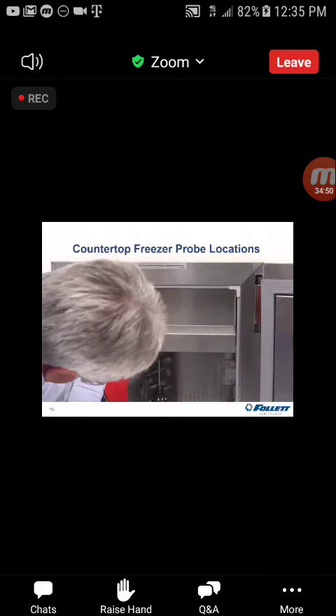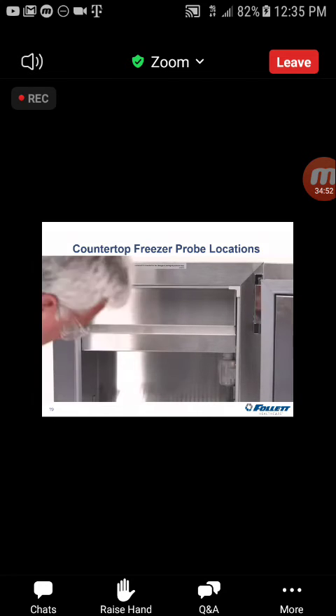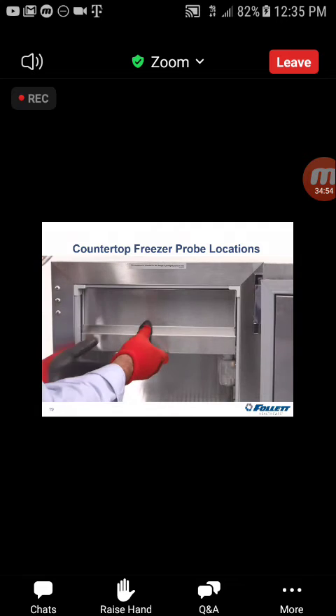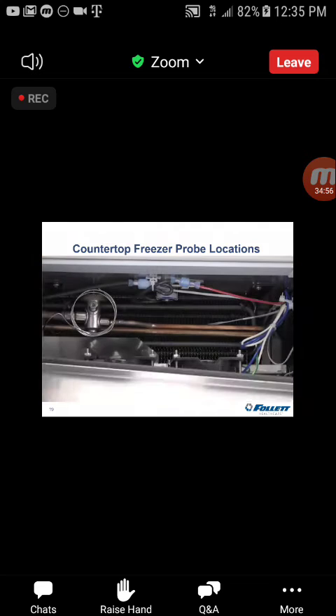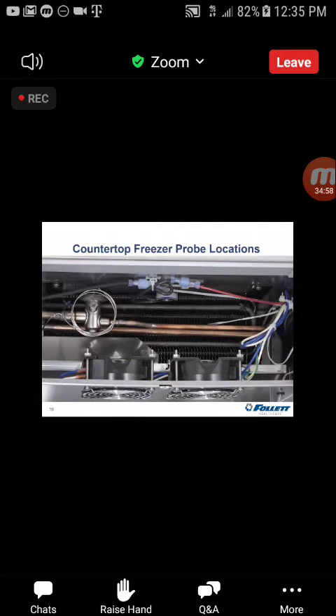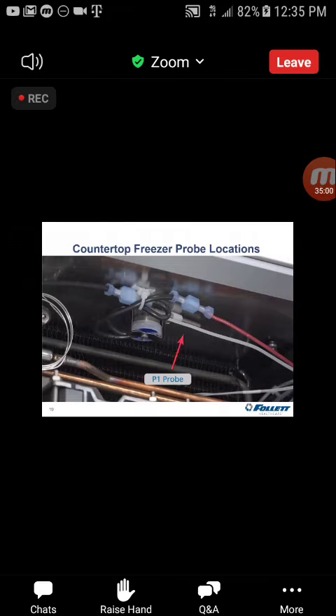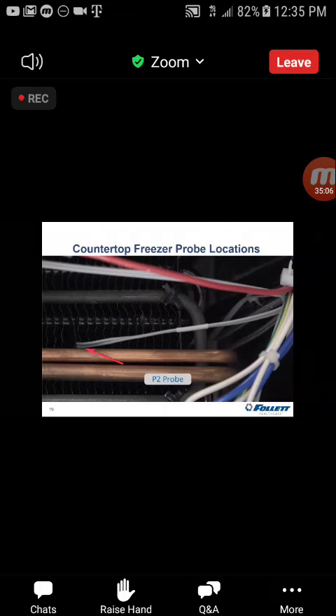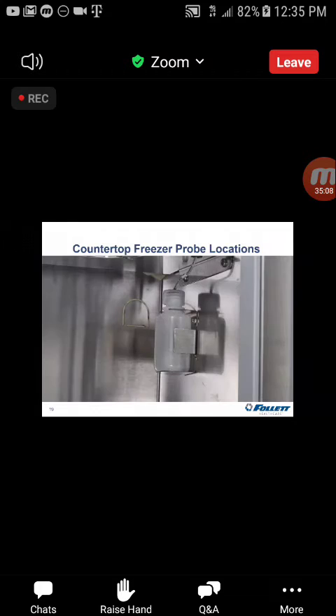To access the P1 control probe or the P2 defrost termination probe, remove the single vertical Phillips head screw from the assembly, remove and set aside the cover plate, and then the P1 probe you'll see mounted on the underside of the top of the unit next to the safety switch, and the P2 probe is in the fin block.